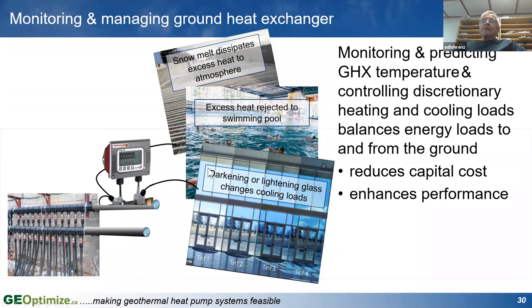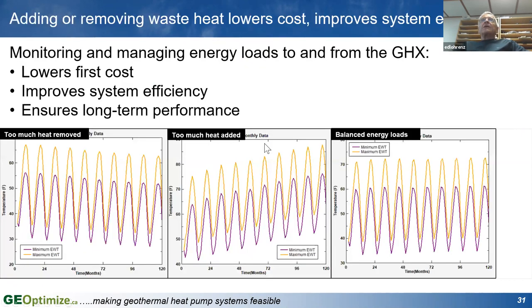So that's starting to come into the industry more and more. Those kinds of different kinds of things. And you can look at a whole bunch of different ways of using energy. You can add solar thermal energy to the ground loop, for example, and add heat to the ground loop if you need to. So what we're trying to do with that is avoid dropping the temperature over time or increasing the temperature over time, make it level, and using loads that we don't really need to service, but we have the opportunity to take advantage of them, we can still maintain the good comfort levels in the building and make some beneficial use of the excess heat that you need, or take advantage of waste heat that you would otherwise dump into the atmosphere. Like combined heat and power, for example, heat can be dumped into a ground heat exchanger rather than just dissipating it to the atmosphere.